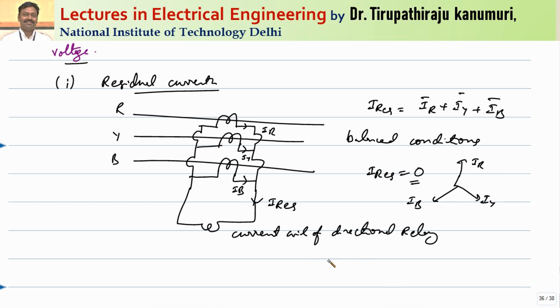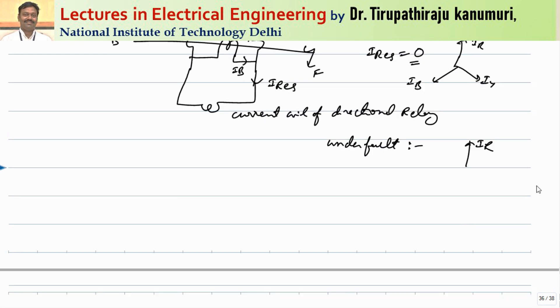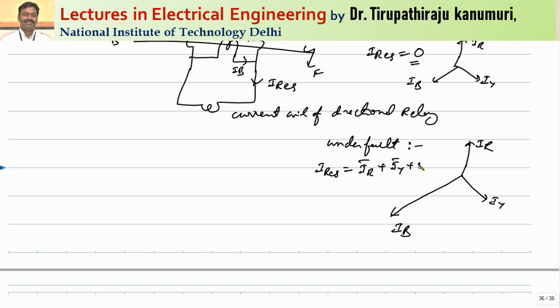Under fault conditions — let us assume the fault has happened in the B phase — the values of IR and IY will be nearly the same, but there is a displacement of IB. So automatically, I-residual, which is the sum of IR plus IY plus IB, is not equal to zero. As the residual current is not equal to zero, your current coil will be actuated and accordingly your relay will operate.